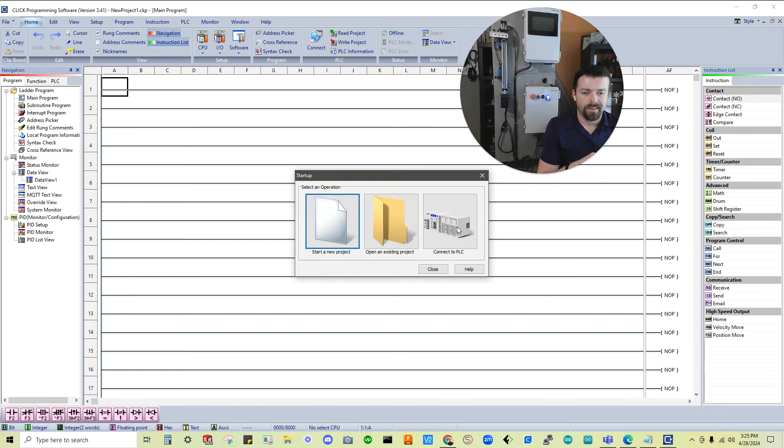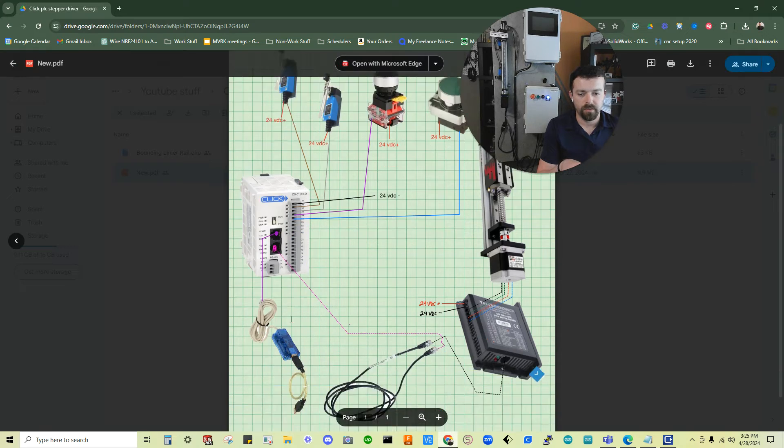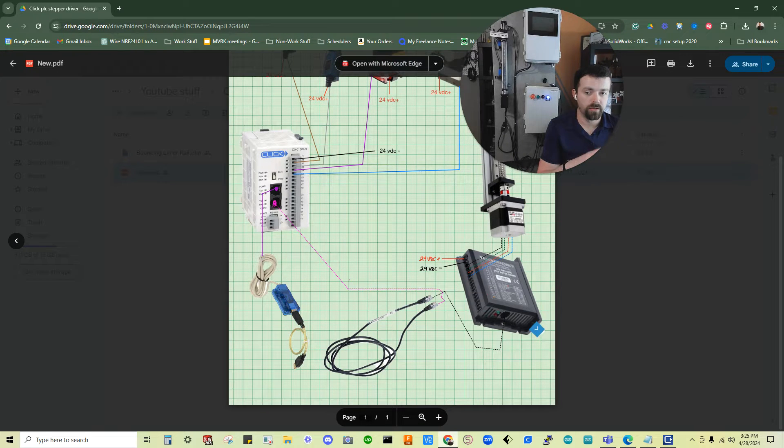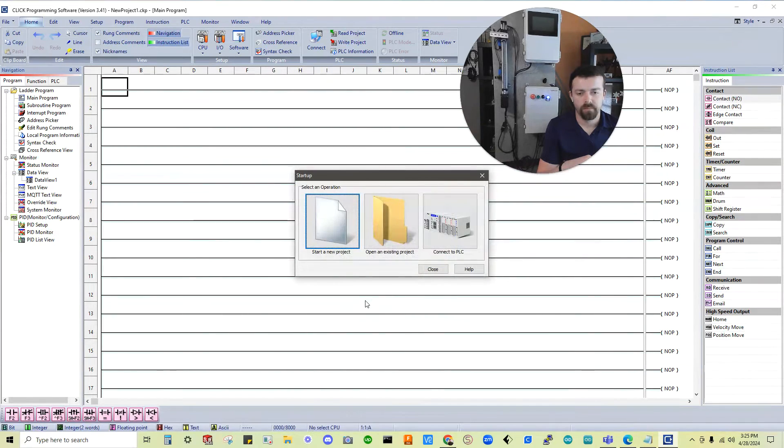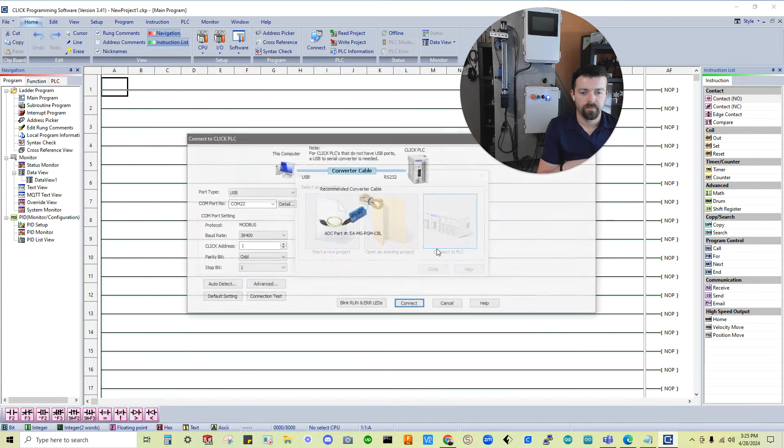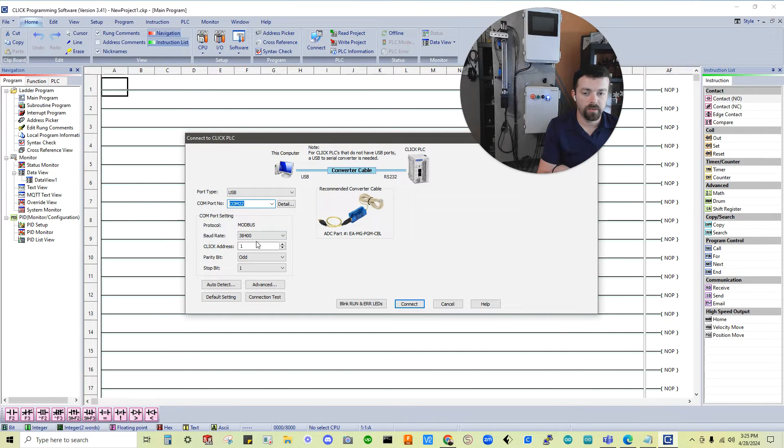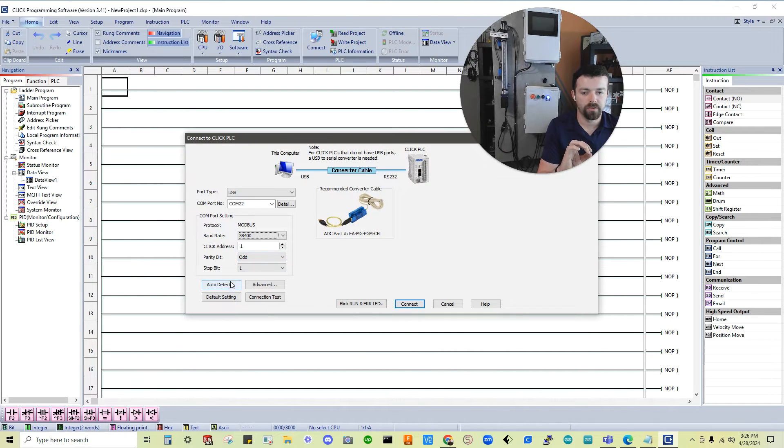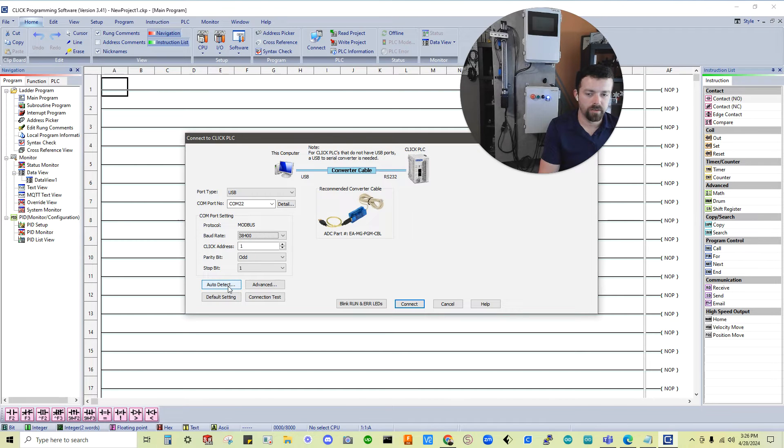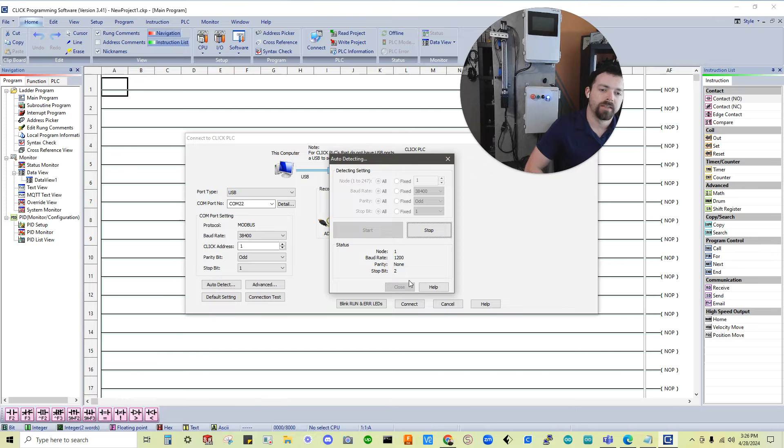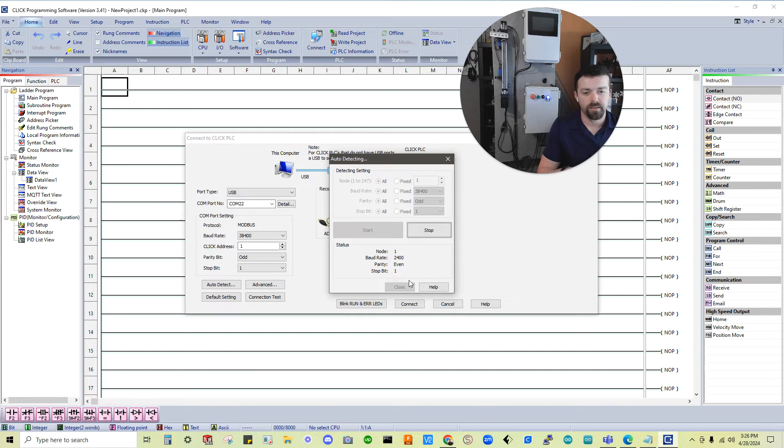Then we're going to say connect to a PLC. Again, you have to connect this cable to your computer, and then to port 1 on the PLC. Okay? So we're going to say connect to a PLC. I'm going to wait for this to open up. If you know which COM port it's on and your baud rate, and you want to set up your parity bits and everything, you can totally do that. Or if you just want to have it do it for you the first time, what you can do is click auto-detect, and then start. This takes a minute, but it'll run through checking multiple in case they've been set to a weird baud rate or something, or you're having trouble finding them. You can see it's just scanning through a lot of different combinations there.